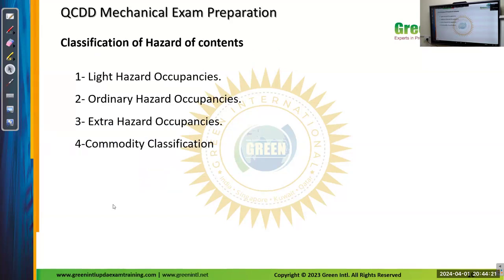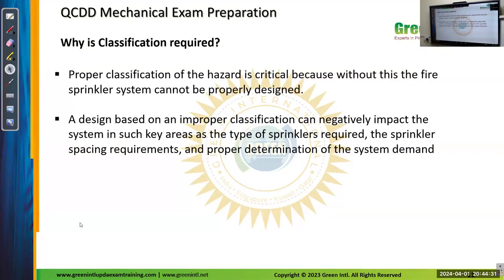So classification of contents. Classification of hazard of contents: light hazard occupancies, ordinary hazard, extra hazard, and commodity classifications. So why is this classification actually required? If we don't know the classifications of hazard, then how will we design the sprinklers, right? Yes. We cannot design sprinklers for ordinary hazard to extra hazard.